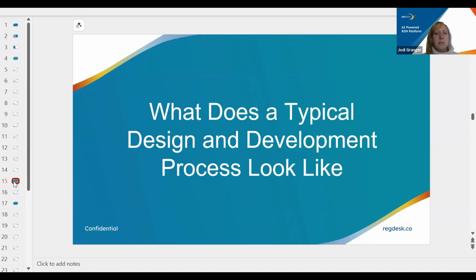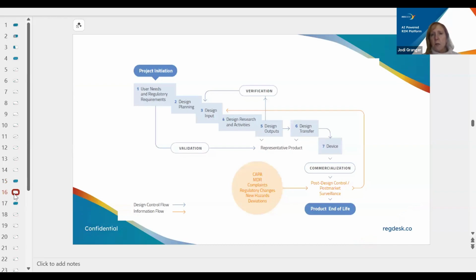So what does a typical design and development process look like? Every company does it a little differently, but essentially this flow chart is pretty standard in the industry in terms of what the process looks like. It is a multi-phased process. It usually starts out when the project is initiated. Someone has a great idea and says, I think we need to create this new device to satisfy this clinician need. So they gather the user needs, and that will also filter in with the regulatory requirements. Design planning is conducted, and ultimately that leads to your design inputs.